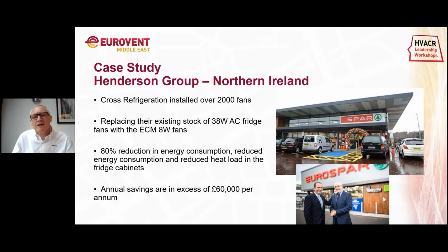Now you could say, okay, that's 30 watts - that's not a huge amount of saving. But in percentage terms, it's huge - it's about 80%. And if you multiply that by 2,000 fans, that's a huge saving. It also put less heat into the cabinet, so the compressors didn't have to work so hard, because obviously that 30 extra watts is heat, and that was dissipating into the refrigeration case. So the refrigeration system didn't need to work as hard. The compressor didn't need to work as hard.